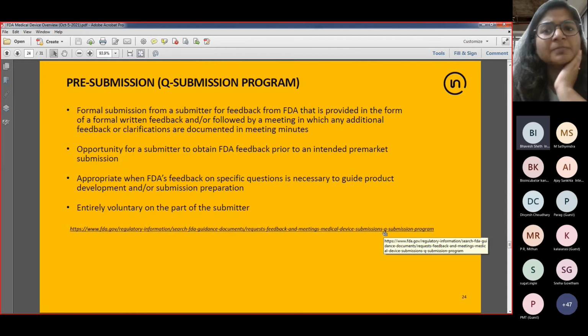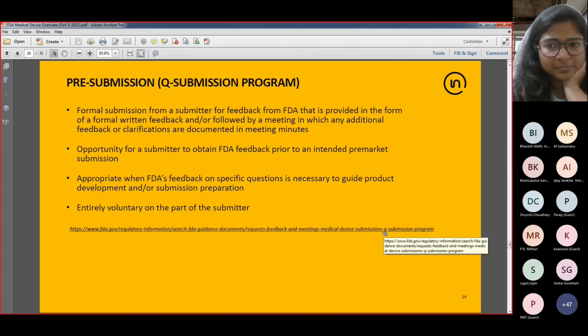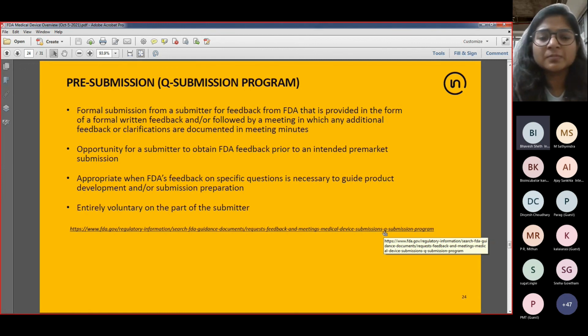But one thing that manufacturers often tend to overlook, and that kind of hits them hard at the back end, is quality management system compliance. So radiotherapy devices, class 2 devices, you have to comply with ISO 13485, medical device QMS. FDA doesn't ask for quality management system documents in 510Ks, but once the 510K is cleared, FDA can perform an audit anytime. They do random audits. So they visit the sites unannounced, and they can ask you for proving compliance with quality management system and any other good manufacturing practices evidence. So those are the additional things I would recommend keeping in mind just beyond the 510K.